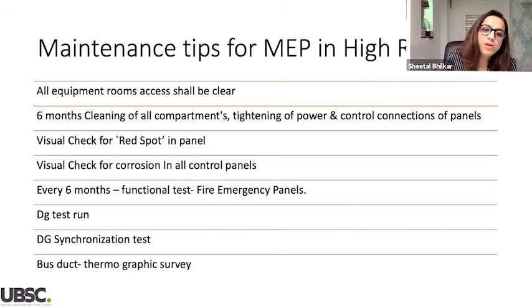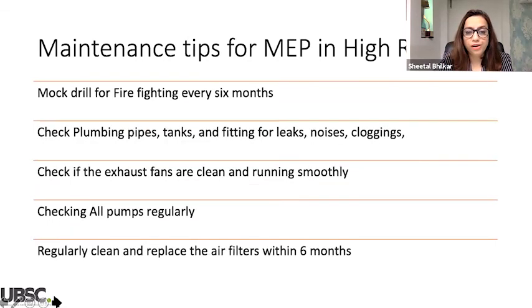Then even the DG test run should be done, because in Mumbai usually the electricity is not shut off and power failures are not frequent, so the DG is not running, and when the actual need is there, that DG does not function. So this DG test run is also important. DG synchronization test, bus duct thermographic survey, all these things are very important. Even a mock drill for firefighting every 6 months is very important.